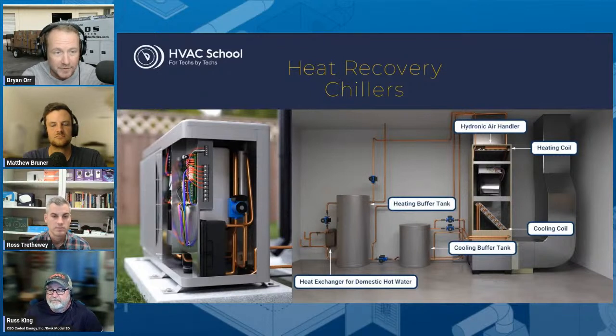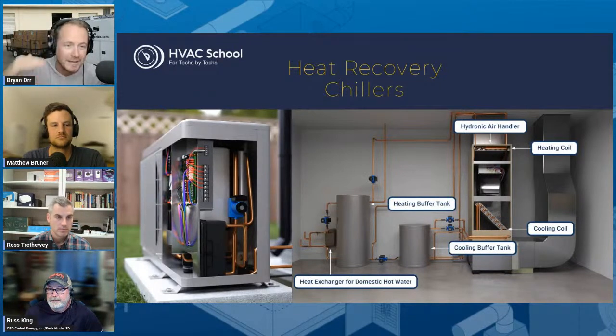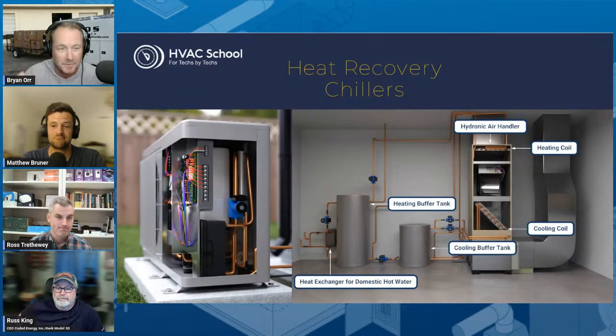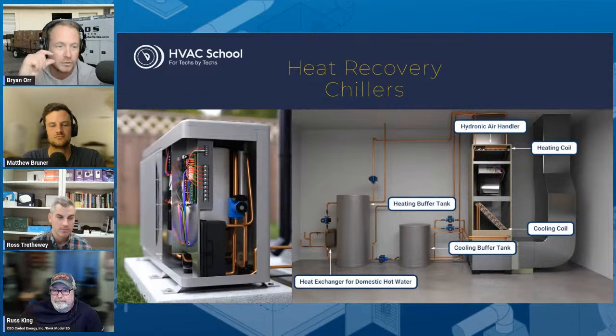And not just a dehumidifier, because a lot of dehumidifiers, when you install them, are blowing warm, higher temperature air. By using mixing valves and other things, you could control that. So you're literally dehumidifying and blowing back in lower humidity at essentially the same temperature as your indoor air. Which would be super powerful, get better mixing, especially for low load homes. But then you also have the benefit of not having to rely on peak periods of consumption. You could basically produce cooling and heating at a much lower rate constantly with a smaller unit.